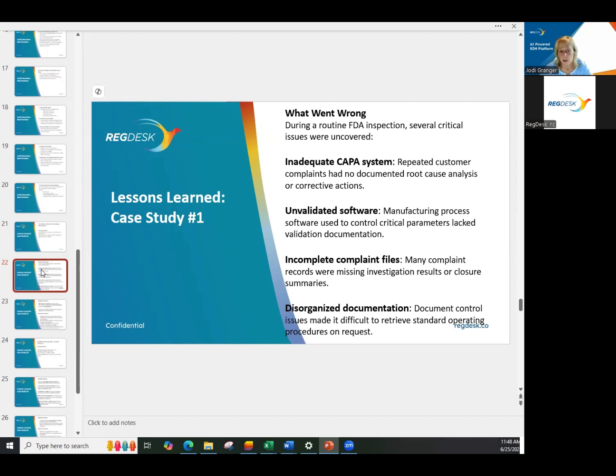The second observation was in regards to unvalidated software. The software actually used to control critical parameters in the manufacturing process lacked any type of validation documentation. So although it was intended to control, they never proved that it would adequately do that. In addition, they had incomplete complaint files. Many complaint records were missing investigation results or closure summaries. So that was noted as a finding.